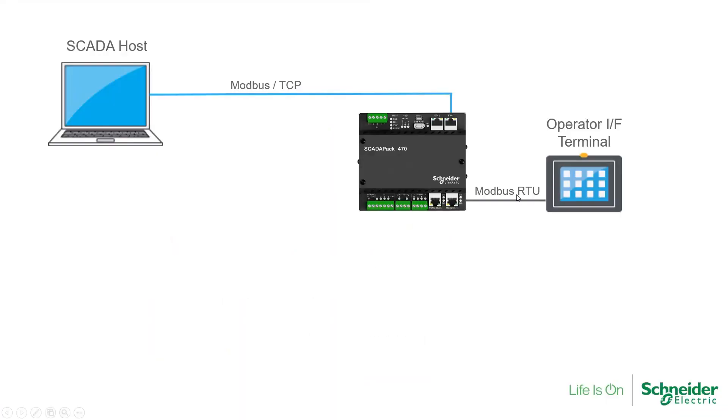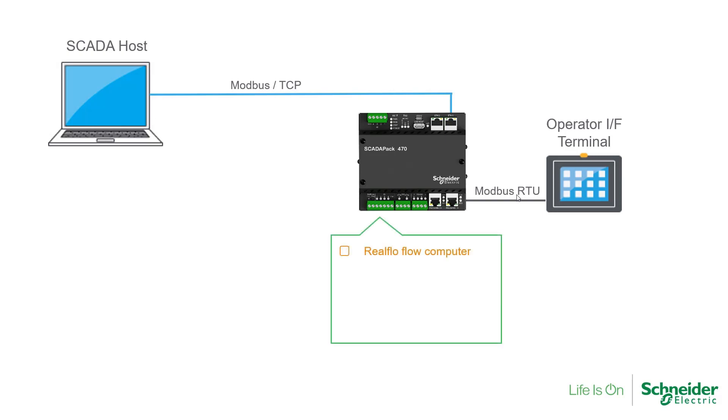Therefore, if you're enabling Realflo in an existing X70 project that already uses the Modbus RTU or Modbus TCP protocol in server or slave mode, then the 32-bit byte order configured for Realflo will affect these Modbus connections as well.